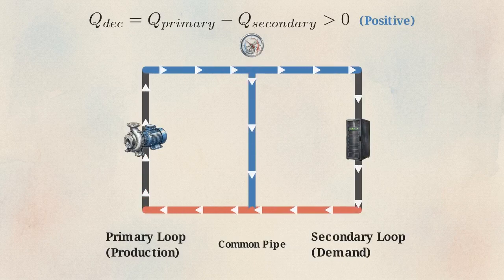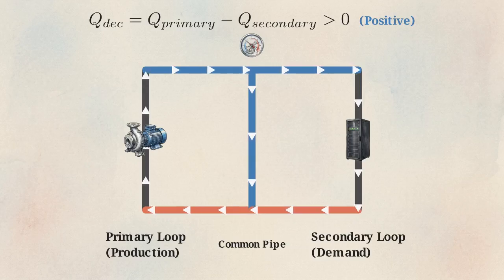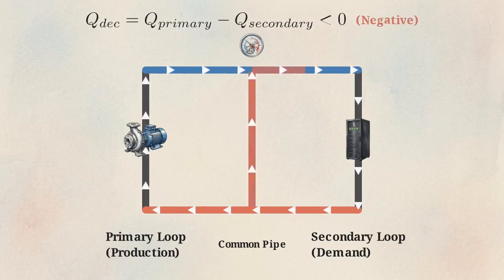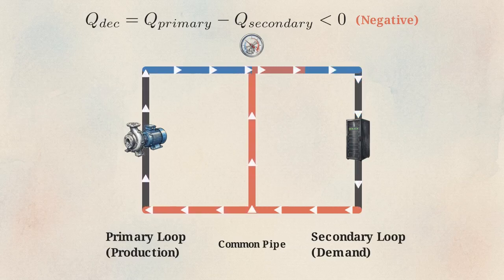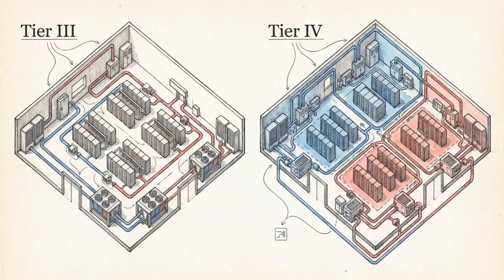Decoupler flow is calculated by subtracting secondary flow from primary flow. The resulting sign indicates the direction of the water, which flips depending on whether the chiller plant is overproducing or underproducing relative to the data center's demand. How a system responds to that demand depends on its tier architecture.